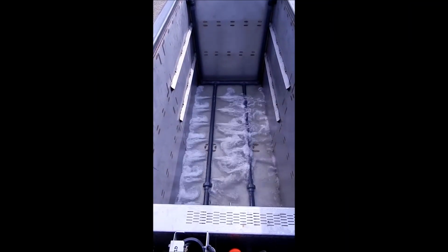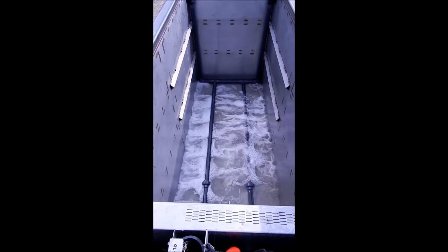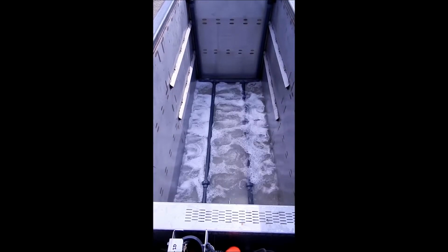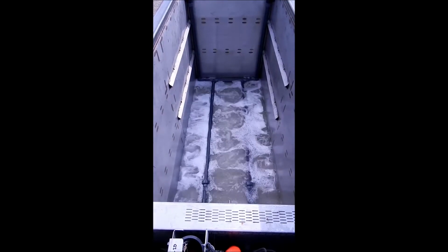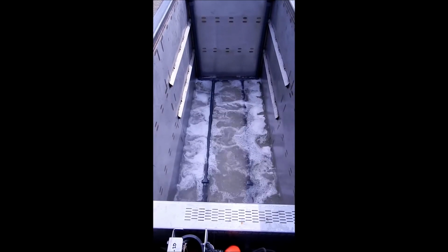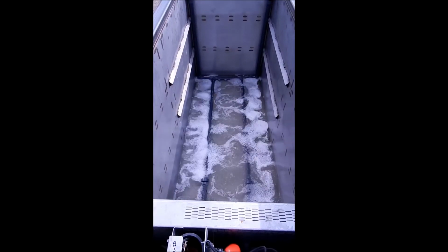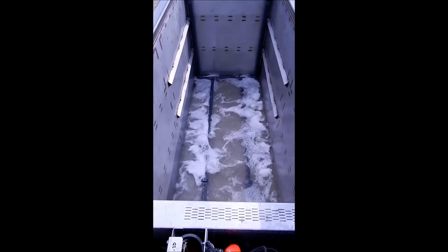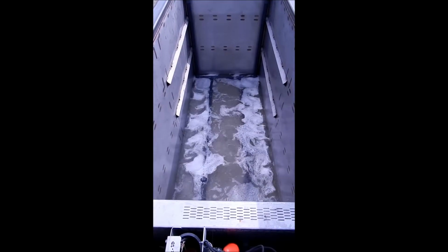The spray bars direct water from the water tap blending valve up through undissolved salt. The stirring action that results dissolves salt, bringing brine up to the proper salinity quickly, and ensures that brine moving through the baffle remains fully saturated until the salt charge is exhausted.